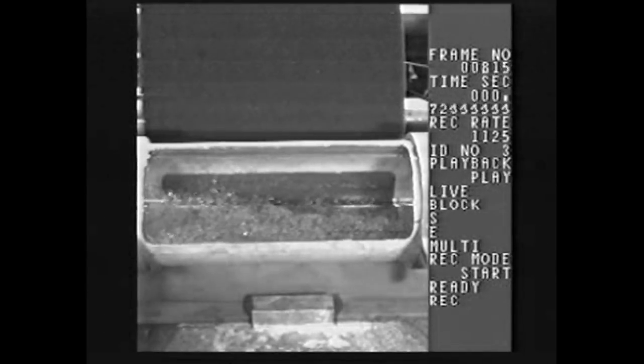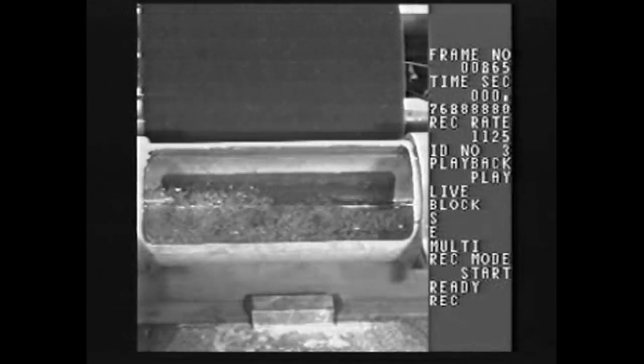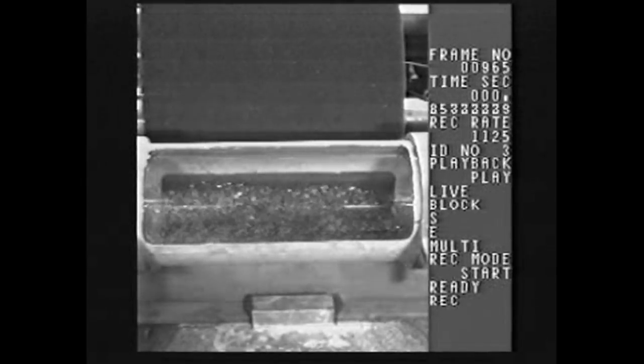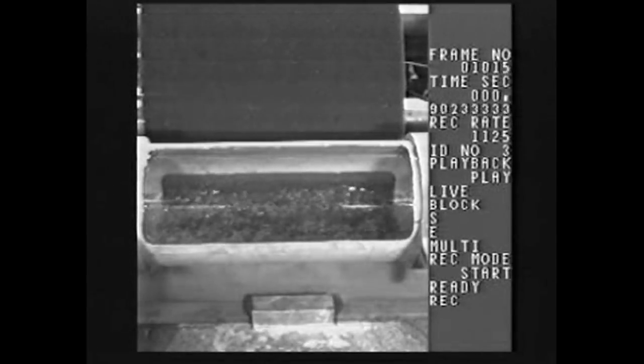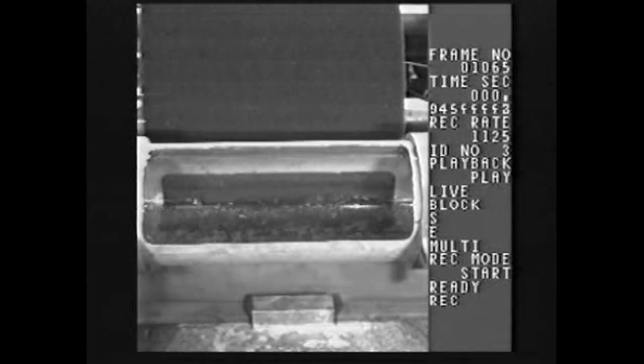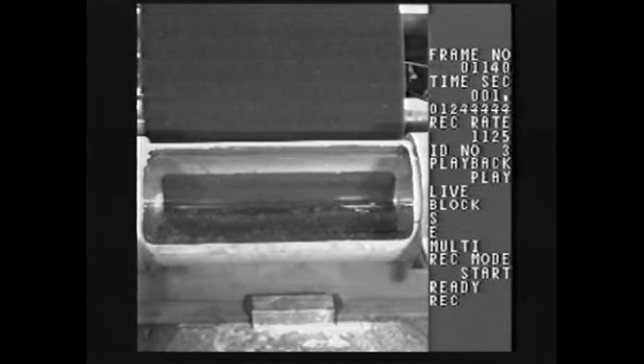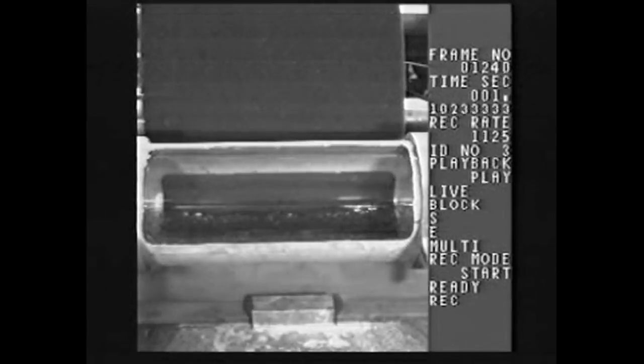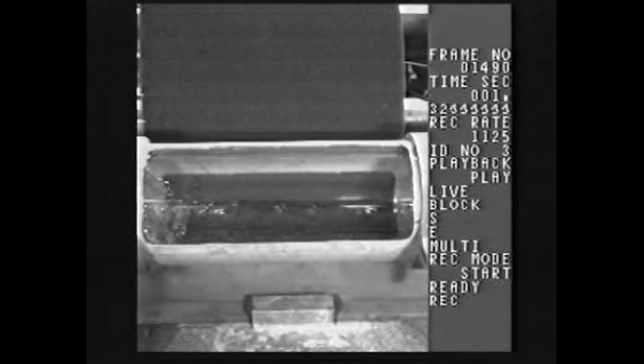Again in this example, Schedule 40 steel pipe, wave speed of 3280 feet per second. That wave oscillates out—you'll see from a full pipe where we now have a partially filled pipe as we pull the vacuum in our piping system. You can see a very defined water line here, and every once in a while you see some off-gassing because you're pulling a vacuum in the water. Then a full vacuum—of course water can't exist, it's going to start to boil.